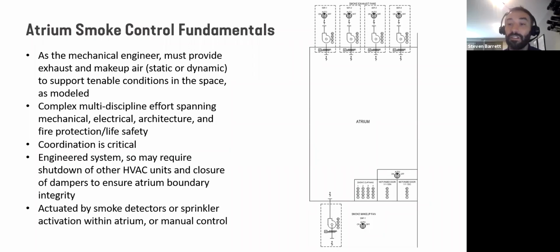And this is an engineered solution. It's a performance-based design. So this very well could, and probably will, require shutting down of other HVAC units unassociated with, but located within, the atrium, and then closing dampers along the atrium boundary to ensure the integrity of that boundary. So that when we do start exhausting and making up air, we have a reasonably tight boundary and we're not spreading smoke to other spaces, and we are able to ensure these tenable conditions throughout the occupant evacuation.